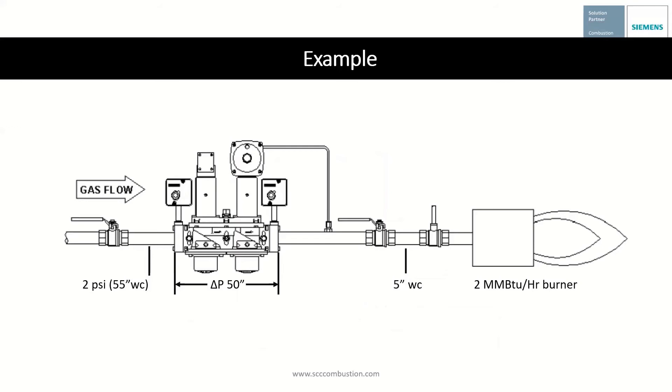For calculations by hand, we'll go through a short example. In this case, we have 2 psi inlet pressure and 5 inches water column gas pressure required at the burner. This gives us 50 inches water column of available pressure drop. The goal is to size the shutoff valve to take as much of the 50 inches water column available pressure without going over. We have here a 2 million BTU per hour burner.